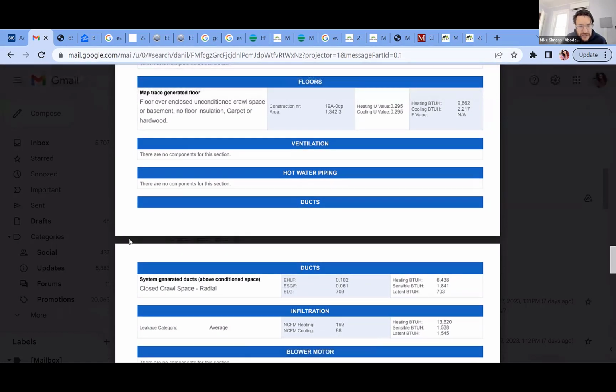Oh, this is actually interesting. So right now you don't have any ductwork, correct? Right. Yeah, so for some reason they added in 6,000 BTUs worth of duct losses. So that's another thing making the load half a ton greater than you would think, because they have no ducts, but they're including duct losses when there are no ducts.